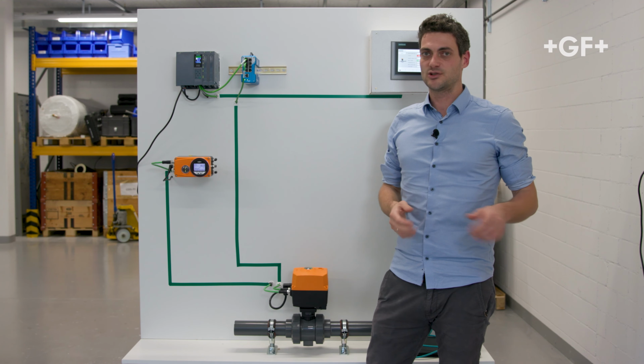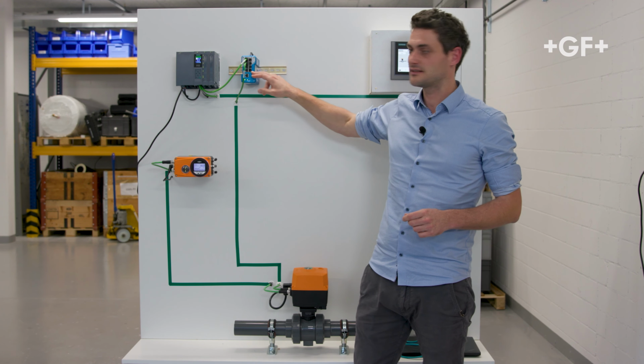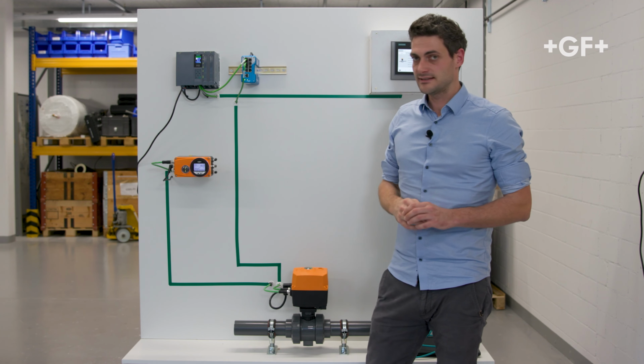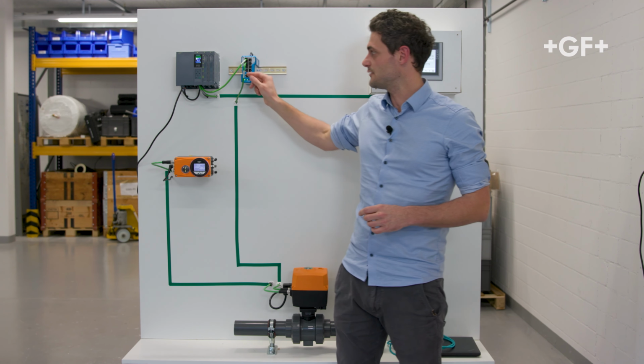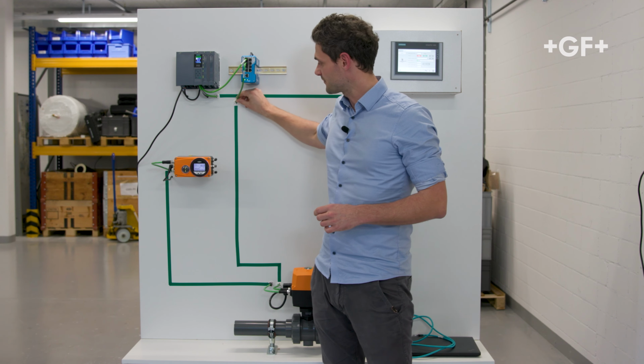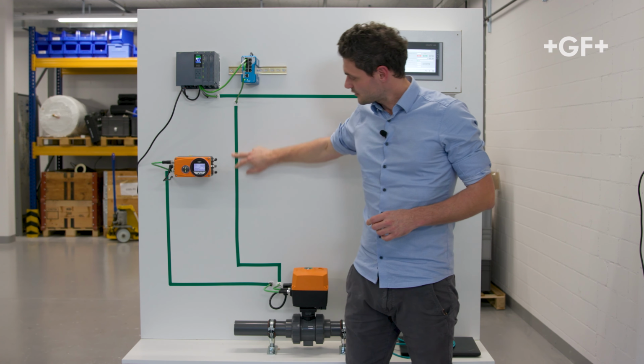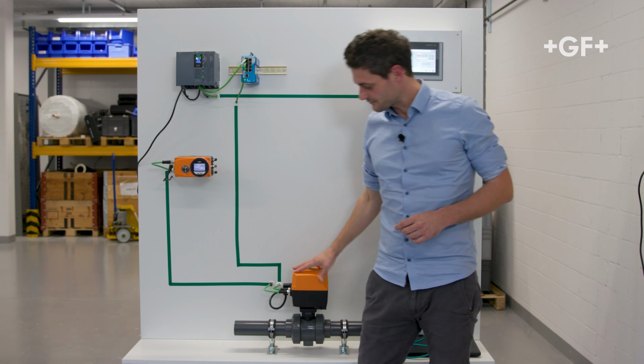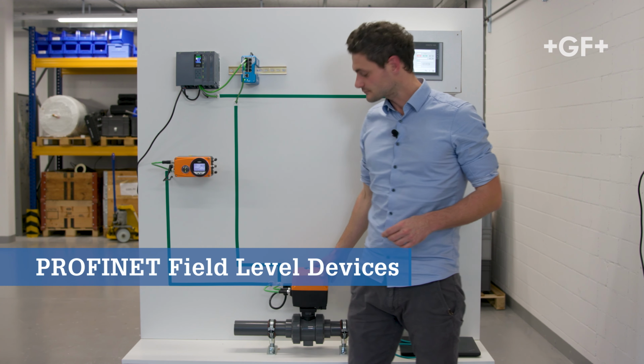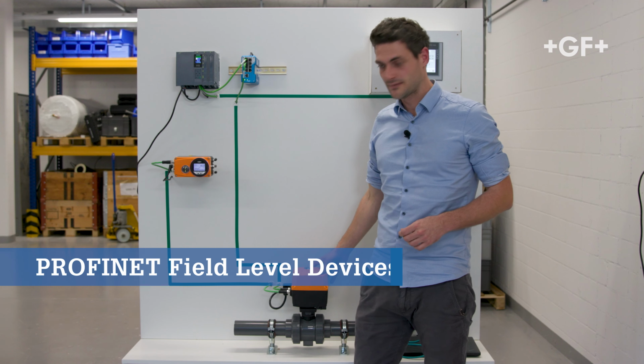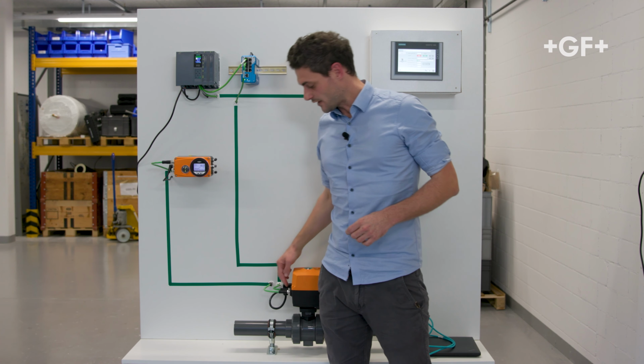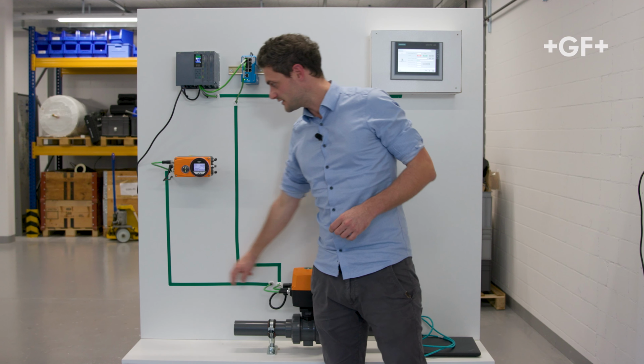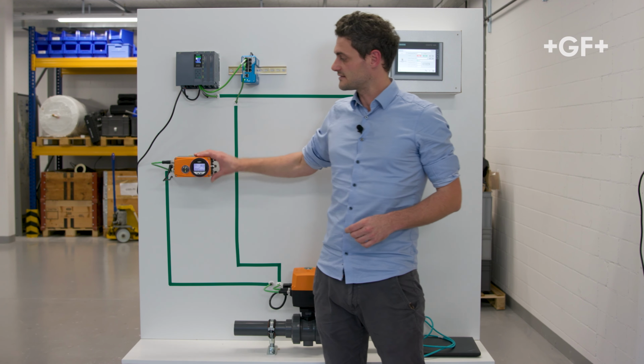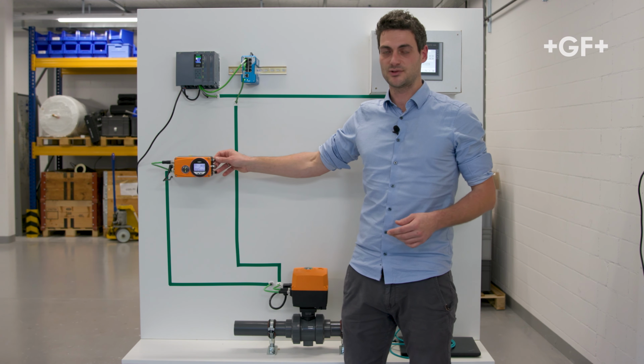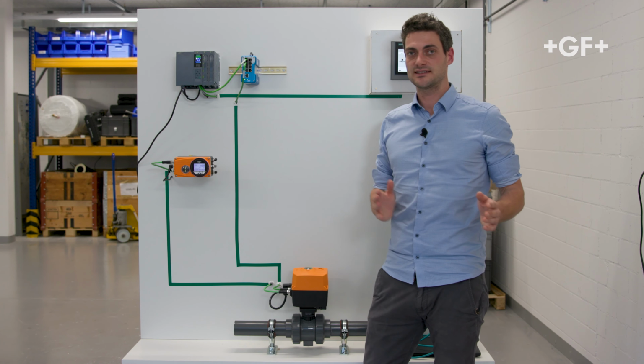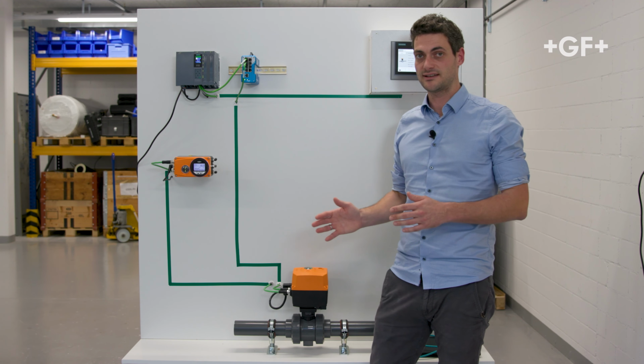either in a so-called star topology, which means I can connect different Ethernet devices to each port here. But Ethernet also offers the flexibility to connect several devices in a so-called line topology. Let's take a look at that. So we have an Ethernet connection here from the switch to the first device. In this case, it's our electric actuator, which is enabled to speak Profinet. From this device, we can go via the second Ethernet port to the next Ethernet device in this line. In this example, this is our positioner for pneumatic actuators. So as you can see, we offer here an Ethernet solution for both electric actuators and pneumatic actuators.